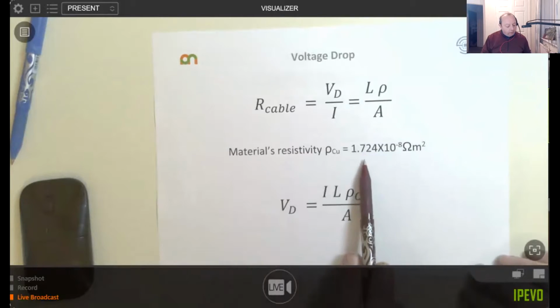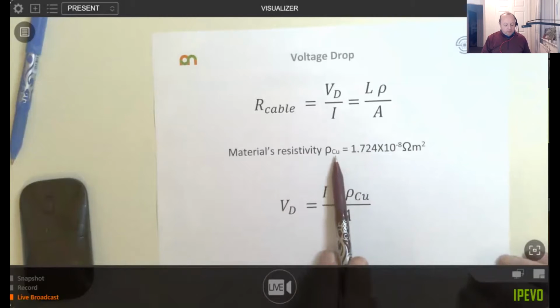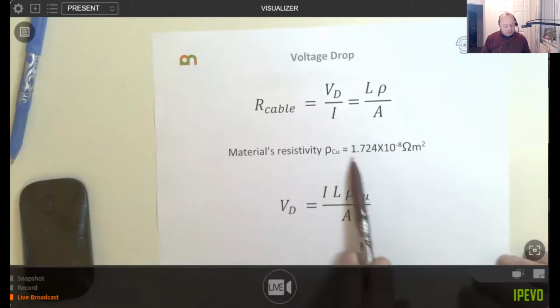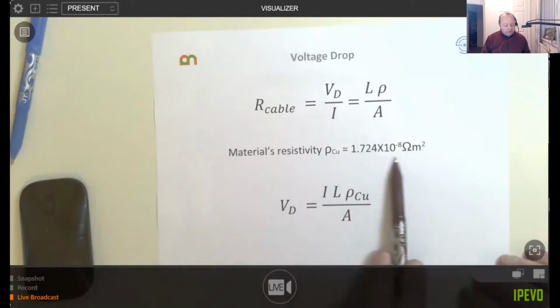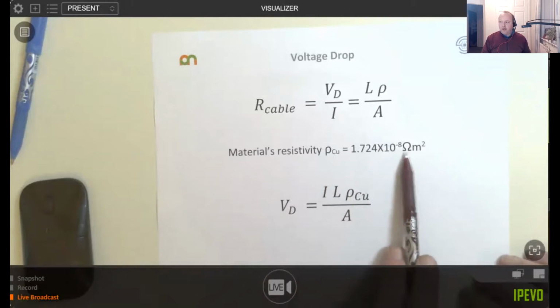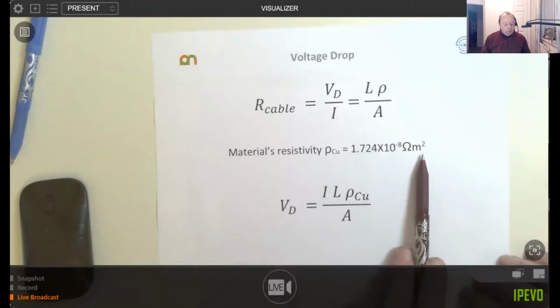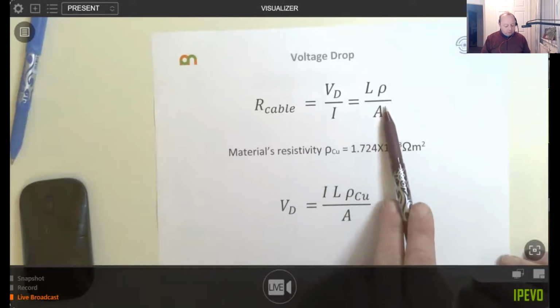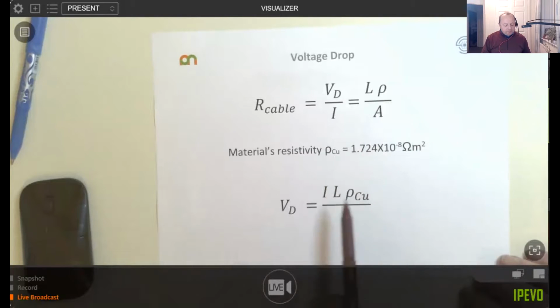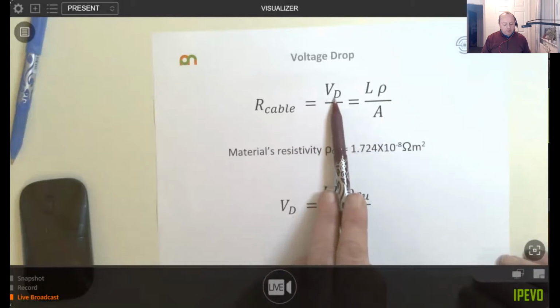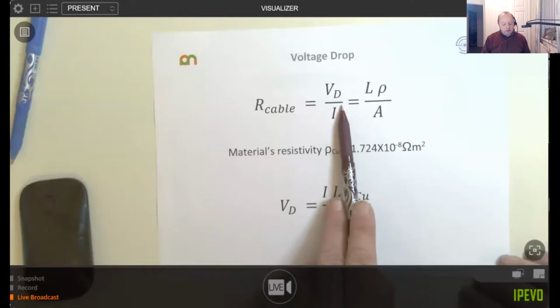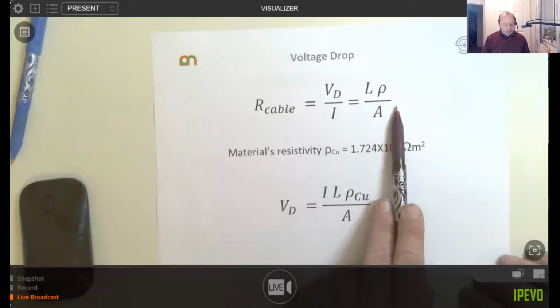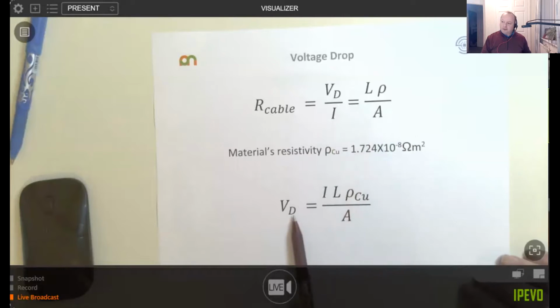For a copper cable, which is why I put Cu, the chemical symbol for copper, someone has worked out what the resistivity is for a cable, and all we need to do is plug that number into our equation. We can easily rearrange it: if we want to know what the voltage drop is, we just multiply this side by a current and multiply this side by a current, and that gives us a rearranged equation. Hopefully that makes sense.